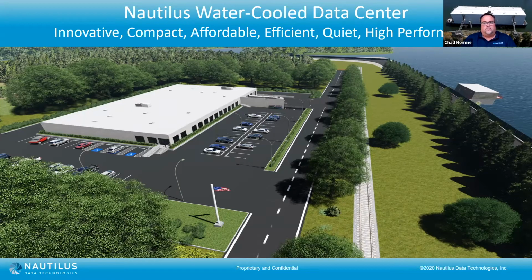For the water in our open loop system, we are water agnostic. Again, we're just borrowing Mother Nature's cold water. We don't care if the water is fresh, brackish, salt, or sewage. As long as it's roughly 75 degrees Fahrenheit or cooler, we are perfectly fine to stay within ASHRAE standards. Similar to what Taylor was mentioning in his presentation, because we are literally just pumps and pipes, and we've been able to eliminate some of the mechanical infrastructure, our footprint is much smaller. If you go to the next slide.